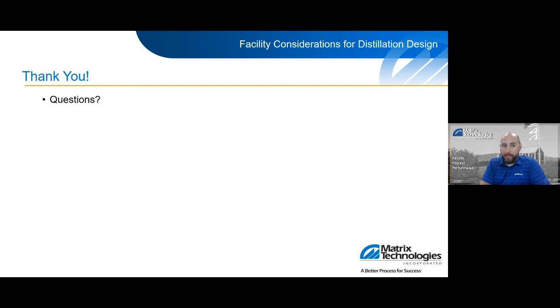I couldn't tell you the specific section. Really, my experience with it comes from the insurance company's driver, that they want to see that backup from a risk liability standpoint. I could definitely do a little more research into the IFC to see exactly where that says that, but I don't know off the top of my head. So then the one that's related to that is, how do you interpret NFPA IFC code as requiring continuous ventilation at all times while processing, or do you have any experience with installations that only activated ventilation once the lower explosive limit was detected, say above 10% at full vent?